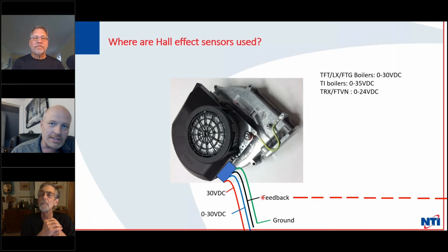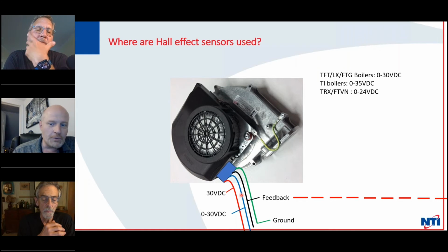So all of our blowers, and I had to use a blue wire here because the white wire on the white screen just doesn't show up. So in the field, that would probably be a white wire for you guys where it says 0 to 30 volts DC. But the colors are kind of irrelevant for the explanation. The way your blower works is it has a feedback line. It's got a ground line so that the electronics inside it know how to work. You've got a voltage signal, sort of voltage hot, so in this case 30 volts DC, and then you've got a variable voltage, so 0 to 30 volts coming in that controls the speed of the blower.